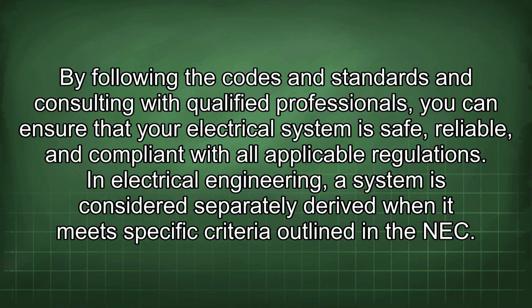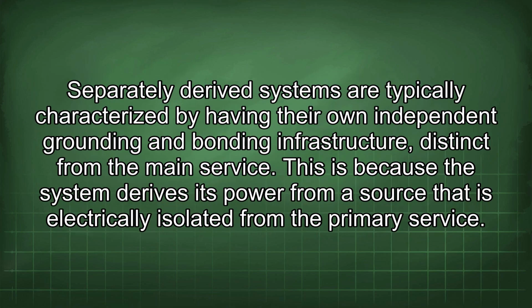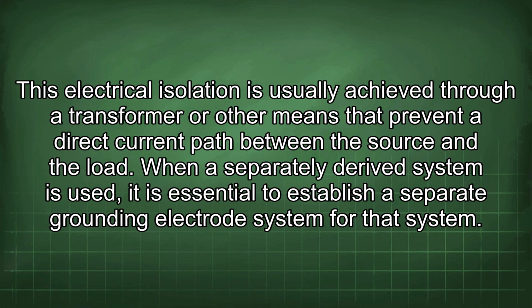In electrical engineering, a system is considered separately derived when it meets specific criteria outlined in the NEC. Separately derived systems are typically characterized by having their own independent grounding and bonding infrastructure, distinct from the main service. This is because the system derives its power from a source that is electrically isolated from the primary service.